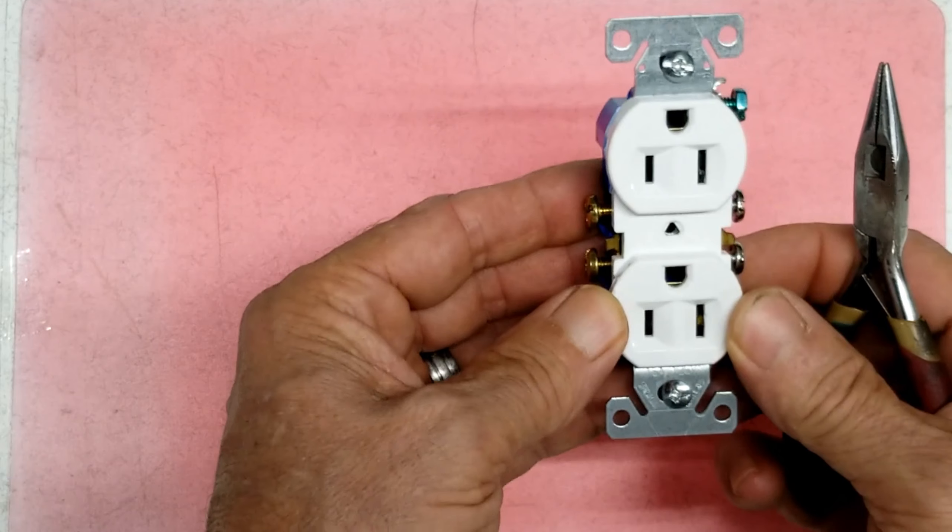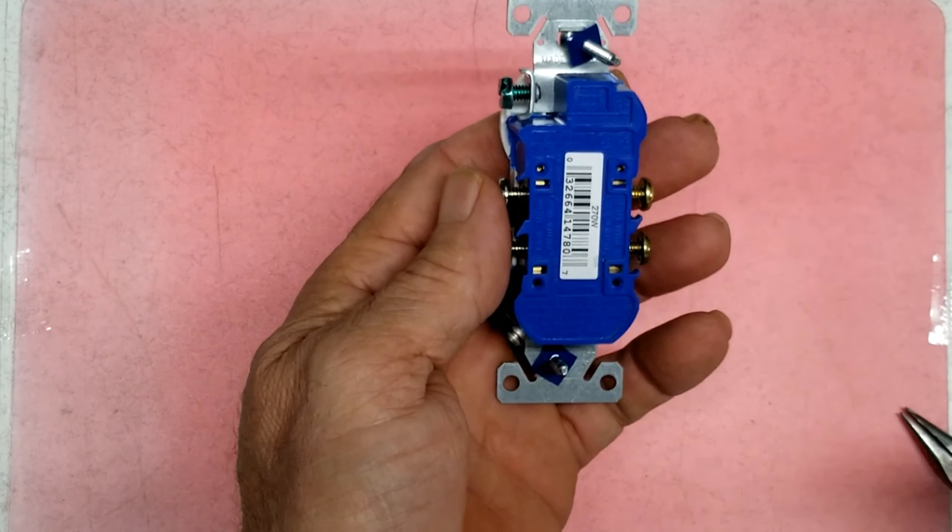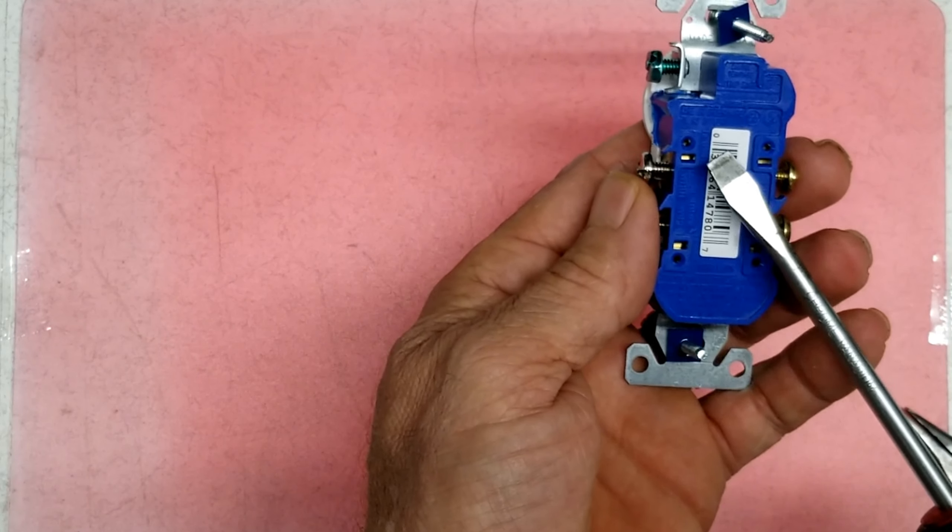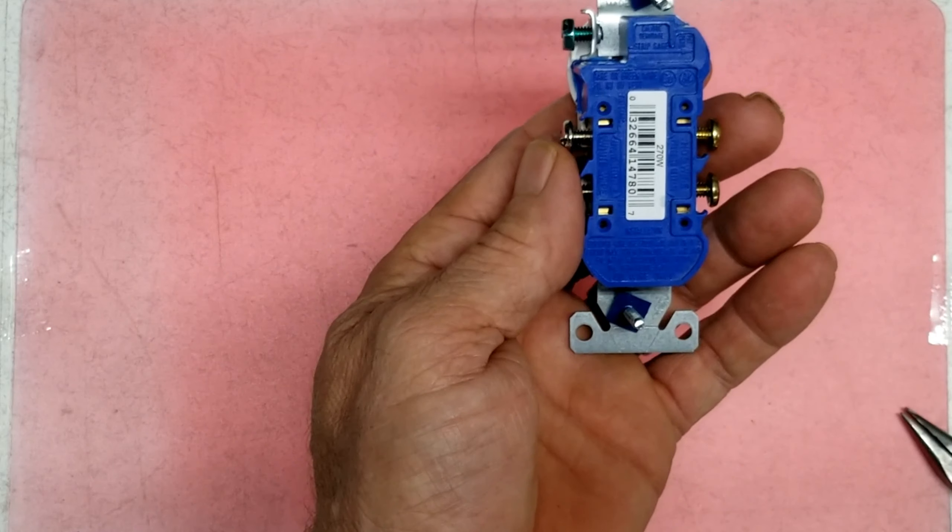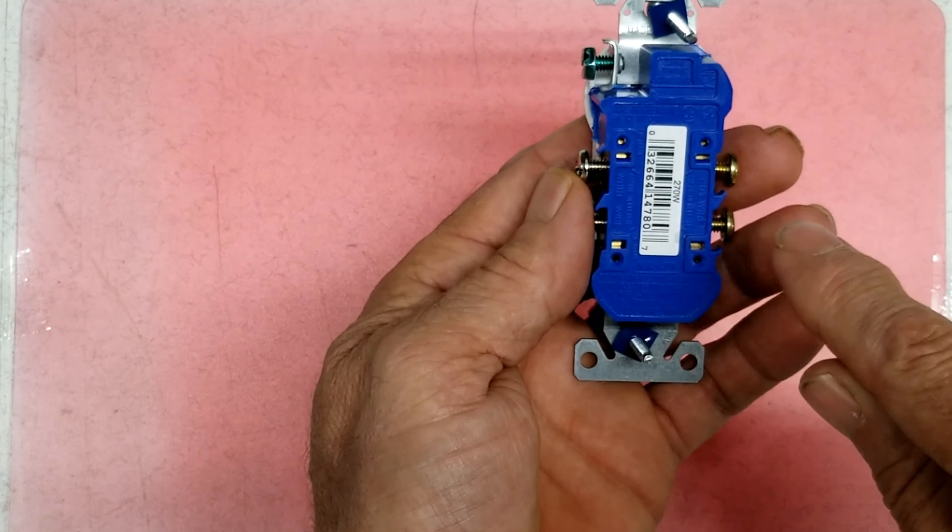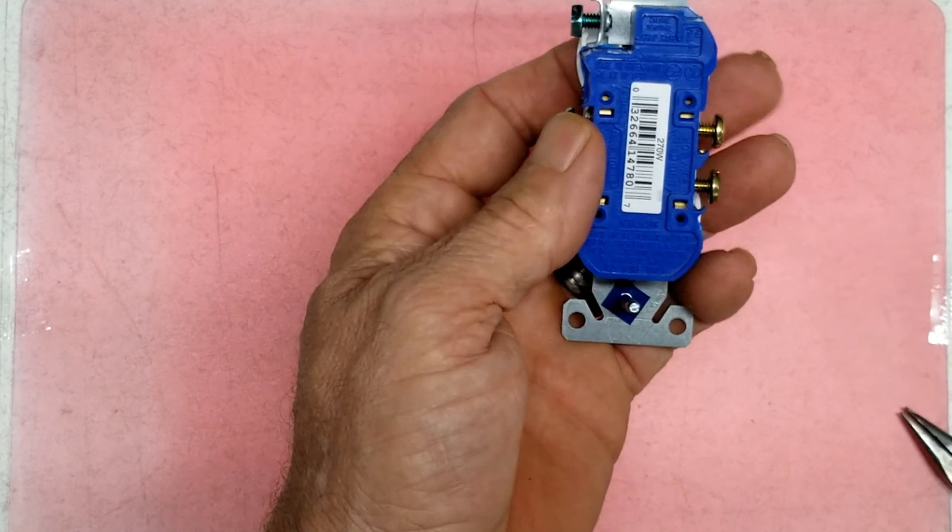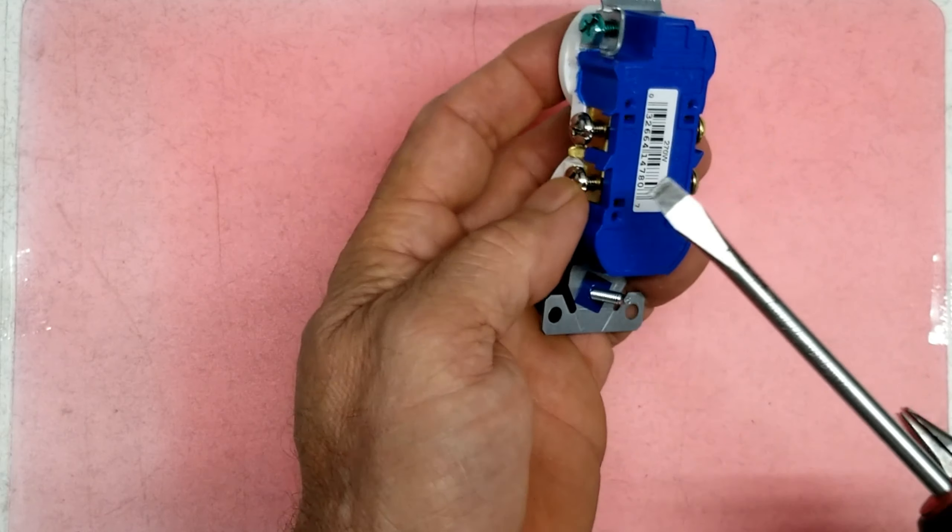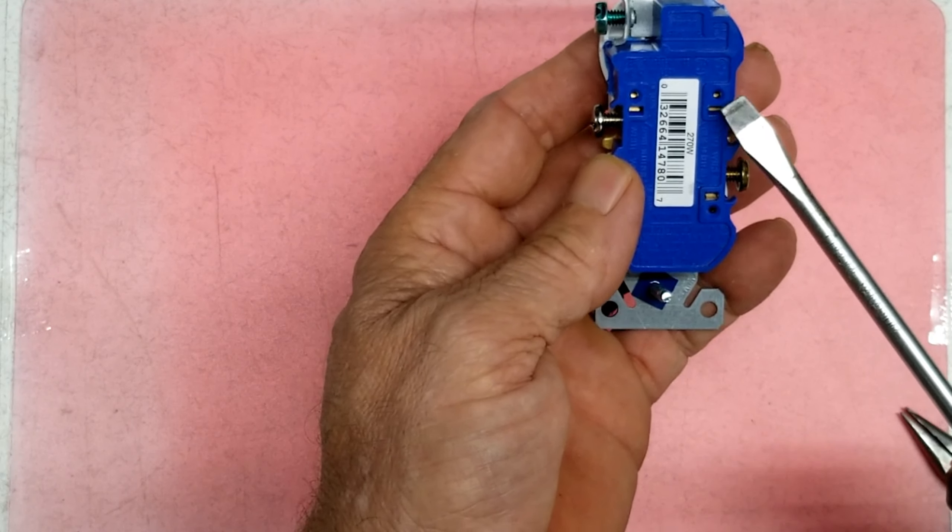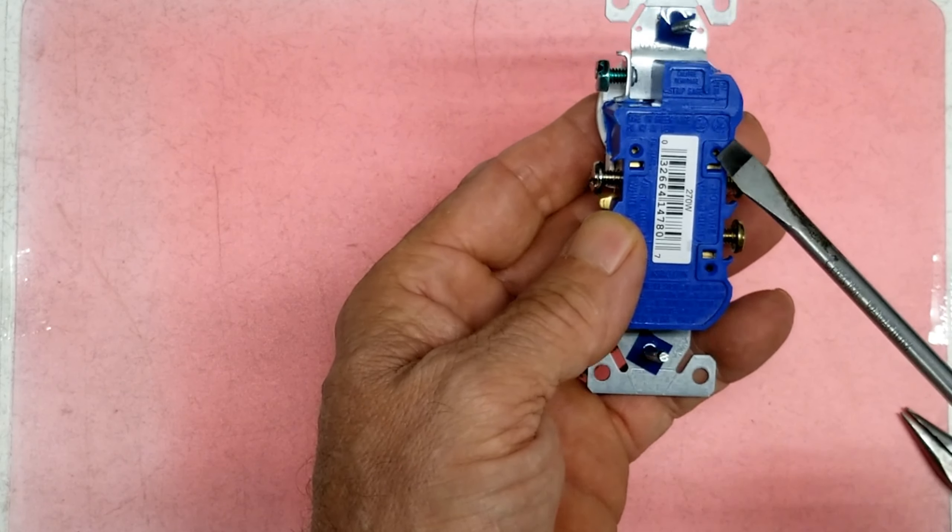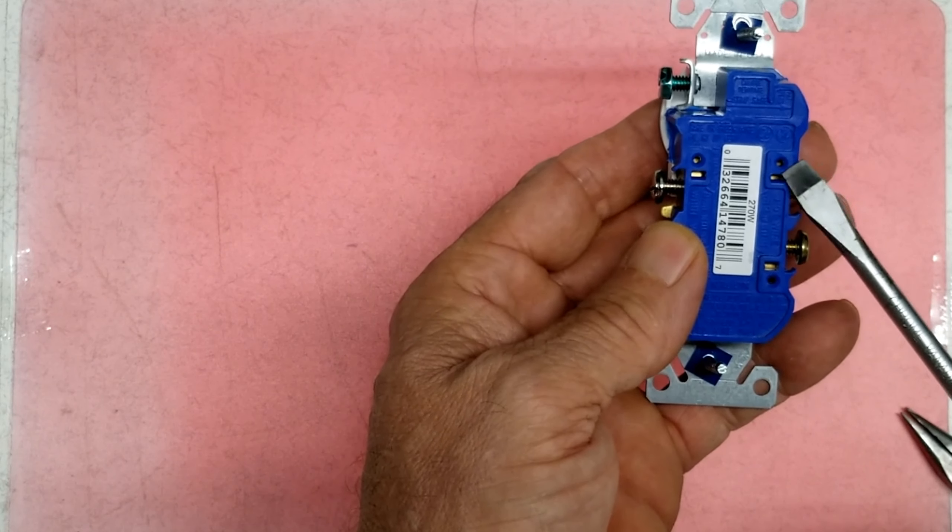All right, on the back of these, you'll see right here they got holes in them. These holes are for a quick fix of pushing a wire in to hook it up. Now, when you change an outlet, the one you're changing may be pushed in that way. But if you've got to change an outlet, put the wires on the terminal screw. Because these here in time will get loose. If you push them in there good and tight, they may be all right for the time being.